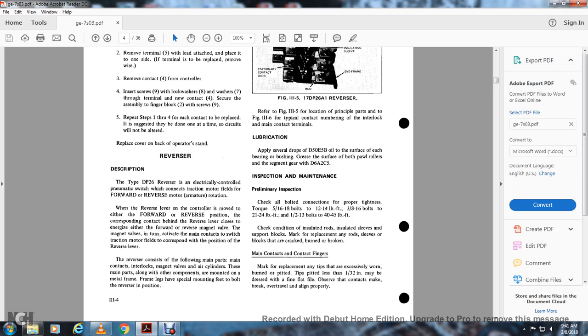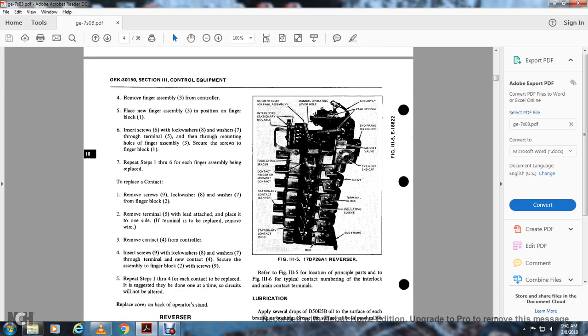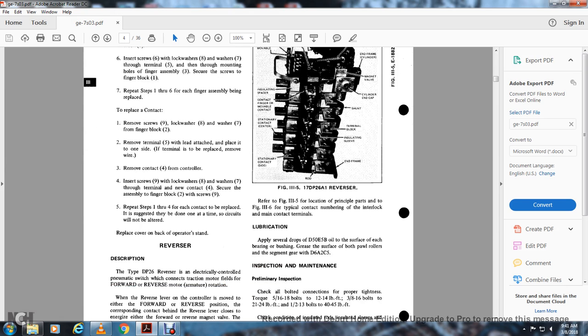The reverser consists of the following main parts: the contacts, interlocking, magnet valve, and the air cylinder, along with the components that are mounted on the metal frame legs, with special mounting feet to bolt the reverser in position. Figure 3.5 shows the 17DP26A1 reverser. Starting at the bottom, you see the rod end frame, insulation sleeve, terminal block, cylinder end cap, magnetic valve, end frame cylinder, pawl spring, air supply, manual operating lever, segment gear or pawl assembly, interlocking stationary movable insulation spacer, contact finger removable point, stationary contact center, stationary contact side. Refer to Figure 3.5 for the location and principal parts, and Figure 3.6 for the typical contact numbers of the interlocking main contact terminals.